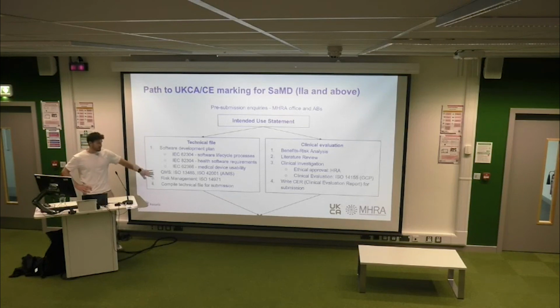You have to have a risk management file, which complies with ISO 14971. This exercise is not dissimilar to the DCB risk analysis. And then you write this all up in a huge amount of documentation.